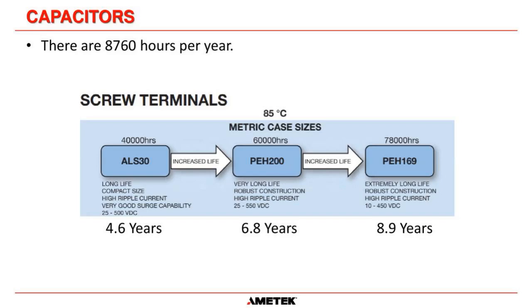Okay, and as I've mentioned there at the top of this slide, there are 8,760 hours in a year. Okay, so for this capacitor here, the ALS30, they're saying that they expect to get 40,000 hours at 85 degrees C, and that works out to 4.6 years. So for this capacitor here, we would recommend that you would replace it every 4.5 years.